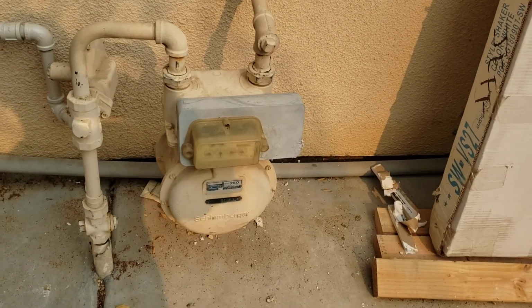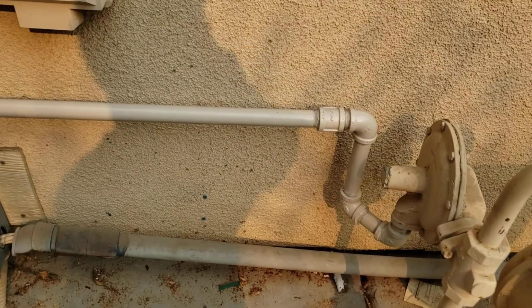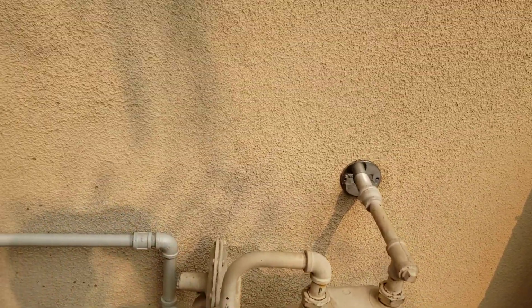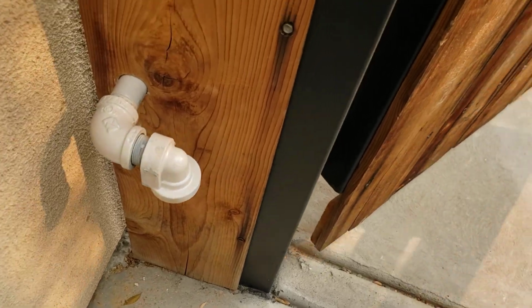So window's going to go in right here, is the gas meter, and the main thing is if you get vent gas out of this vent line on the regulator, it goes into the window. So it needs to be 3 foot away. We're not exactly sure how far this window is going to come over, but we just popped it through right here. You can see nice tight little hole, painted it, so that's good.